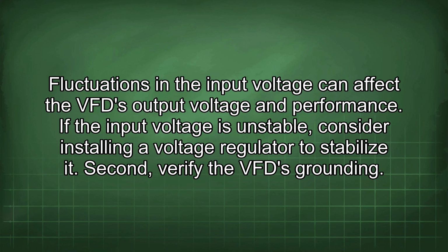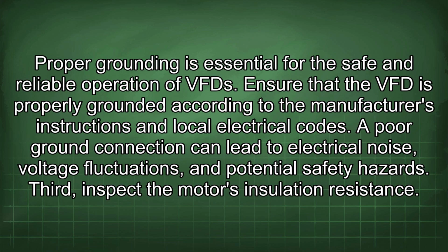Second, verify the VFD grounding. Proper grounding is essential for the safe and reliable operation of VFD. Ensure that the VFD is properly grounded according to the manufacturer's instructions and local electrical codes. A poor ground connection can lead to electrical noise, voltage fluctuations, and potential safety hazards.